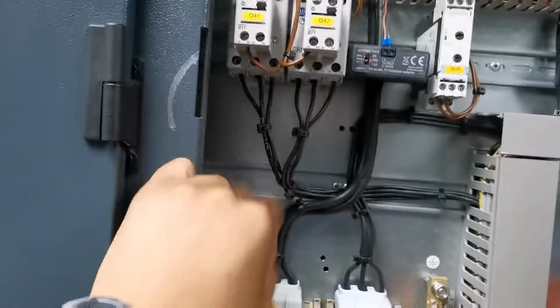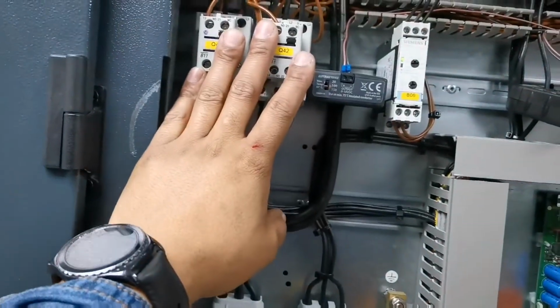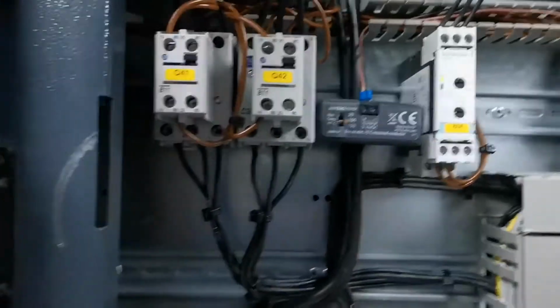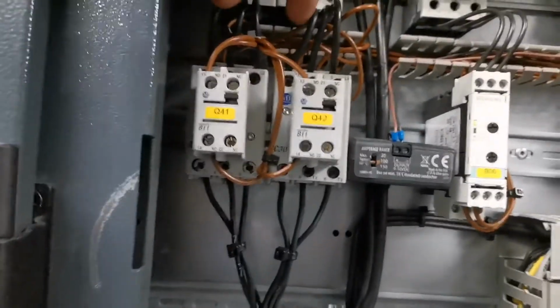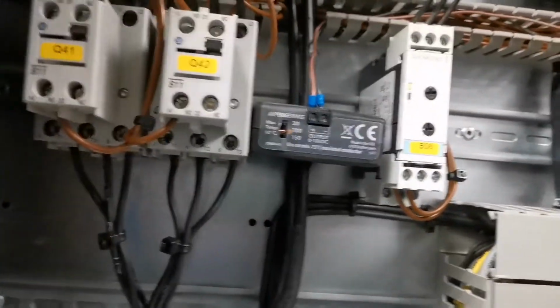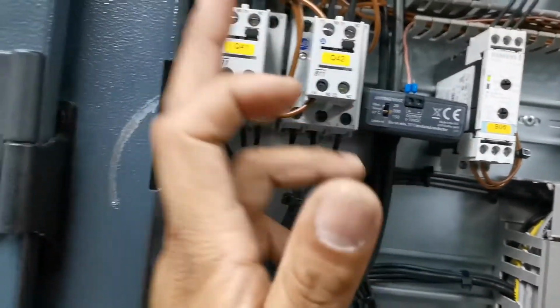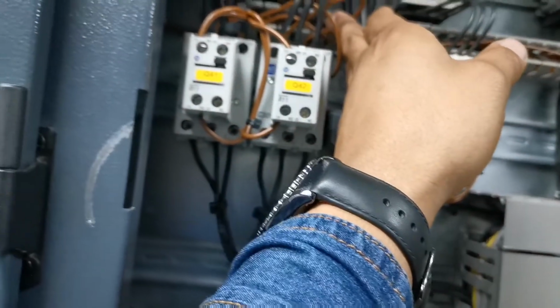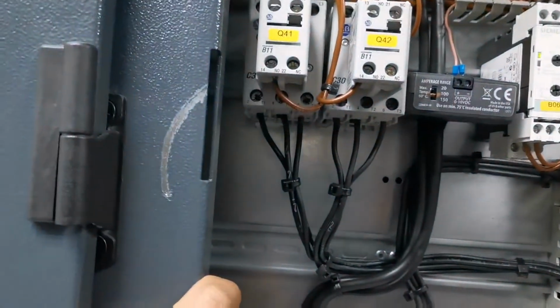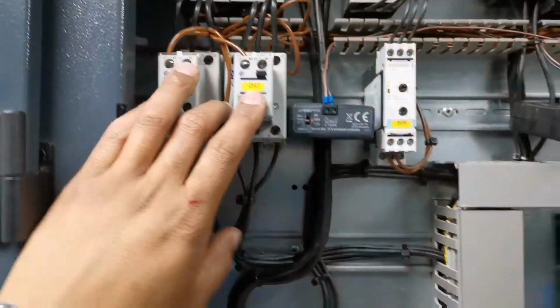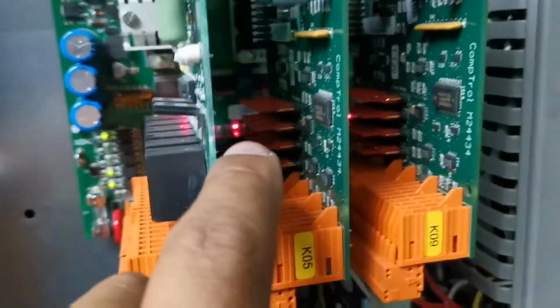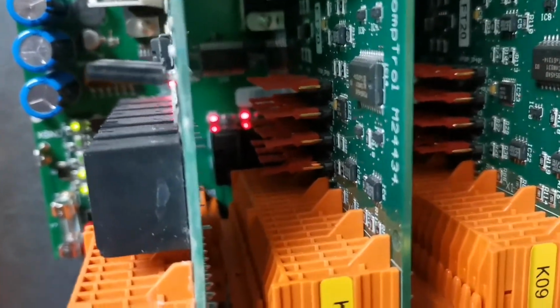So interestingly, on our contactors here, I reinstated everything back the way they were. The only thing that I haven't done was the 24 volt supply to our contactor coils. Compressor 1 is coming to compressor 2 and compressor 2 is going there. The neutrals are in fact the way they have to be, and interestingly everything's running fine. And as you guys can see at the back there, we've got both lights, so both systems are calling for cooling, both circuits. Let me see if I can focus in on that.